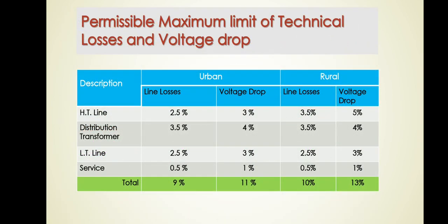We also have different permissible maximum loss limits. The maximum permissible line losses are 9% for urban areas and 10% for rural areas. The overall voltage drop must be below 11%, and for rural it must be below 13%. These are the guidelines that have been given and we must follow them. We are going to discuss the techniques and ways to achieve this. Please stay tuned — I will explain all these concepts in detail from my next video. Subscribe to the channel and press the bell icon so you get immediate information whenever I upload a video on energy conservation and AT&C losses. Thank you very much.